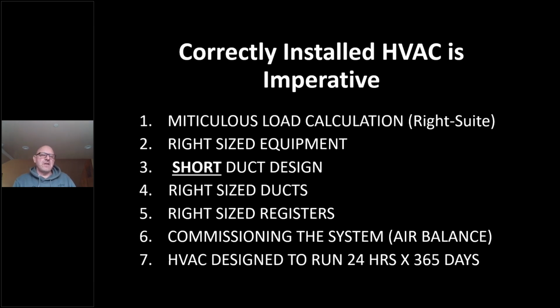Air conditioners that go on and off and on and off just blow up efficiency. And we see this, as I said earlier, in our climate zone when we put in correctly sized equipment that has long running cycles. We see a huge amount of savings, hundreds and hundreds of dollars. So on this particular house, we did a meticulous load calculation, right-sized equipment, short duct design, right-sized ducts, right-sized registers, and, as Larry pointed out, commissioning the system and air balancing. So actually putting it all in, and then bringing it back to our design and making it work how it is on paper. And all our HVAC systems are running 24 hours a day with absolutely no setback, 365 days a year, in the summertime and the wintertime.